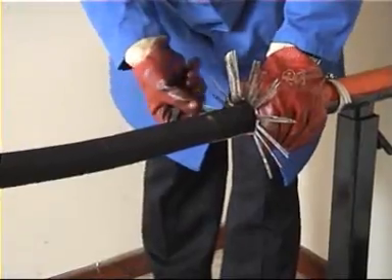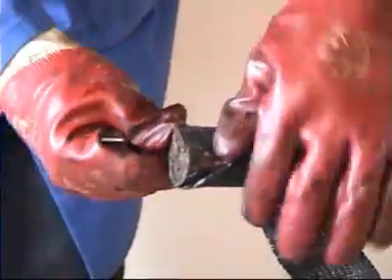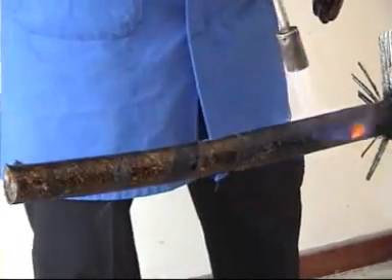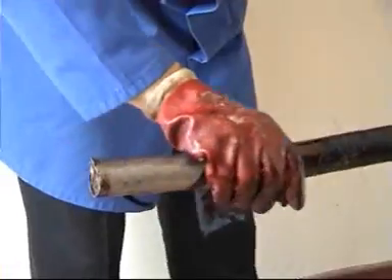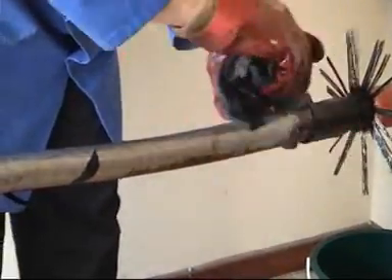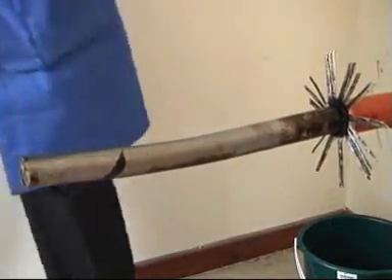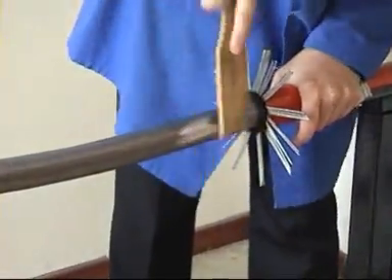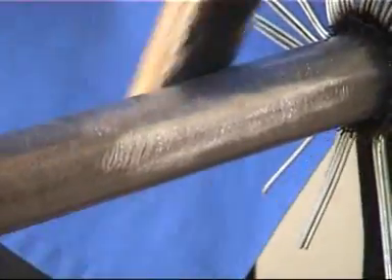In order to expose the lead sheath we now need to remove the bitumastic layers from the cable. Using a gas torch to heat the cable will make this much easier. Use a wire brush to further clean the lead sheath. This will make a good earth connection point.